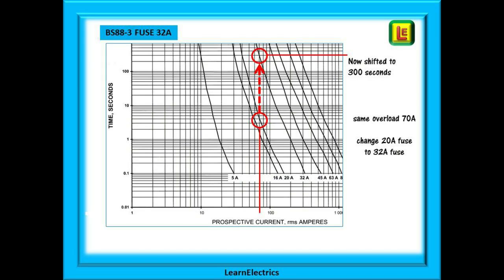Let us look now at the response time for a 32 amp fuse. The same page page 364 with the same 70 amps of overload current the response time is shifted up the chart and it is now 300 seconds.